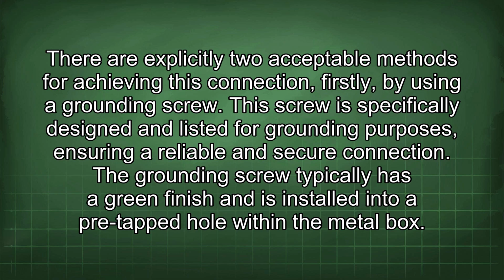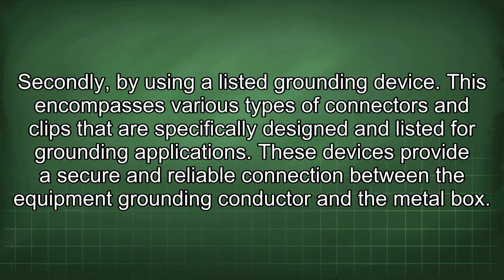Firstly, by using a grounding screw. This screw is specifically designed and listed for grounding purposes, ensuring a reliable and secure connection. The grounding screw typically has a green finish and is installed into a pre-tapped hole within the metal box. Secondly, by using a listed grounding device. This encompasses various types of connectors and clips that are specifically designed and listed for grounding applications. These devices provide a secure and reliable connection between the equipment grounding conductor and the metal box.